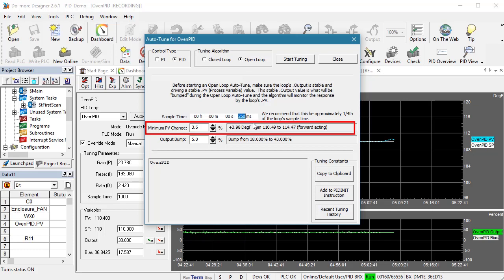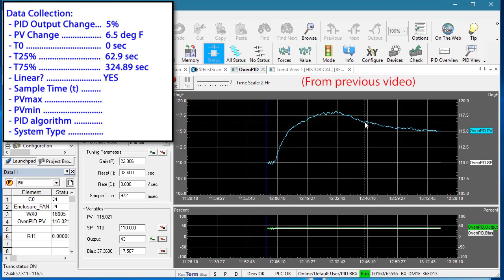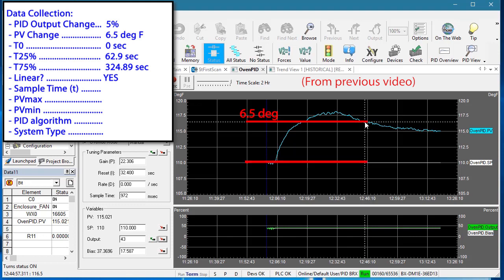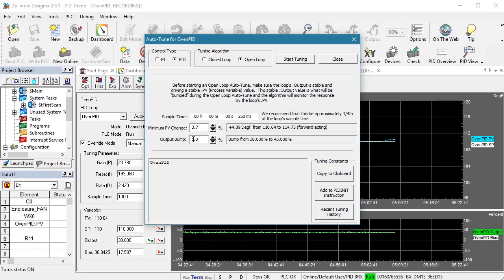Next, it is asking how much the process variable needs to change before Auto-Tune can take its measurements. Auto-Tune wants to measure the rate at which this slope is changing. This gives you control over when it does that. We know from this output bump we did during the manual tuning that a 5% change in the PID output gives us around 6.5 degrees. But most of the serious slope is in this range, so we could probably get away with telling Auto-Tune to take its measurements at around the 2 or 3 degree mark. I am going to set this to get roughly a 4 degree change just so we can see what happens. That was all assuming a 5% PID output change, so I put that here. Hit start.